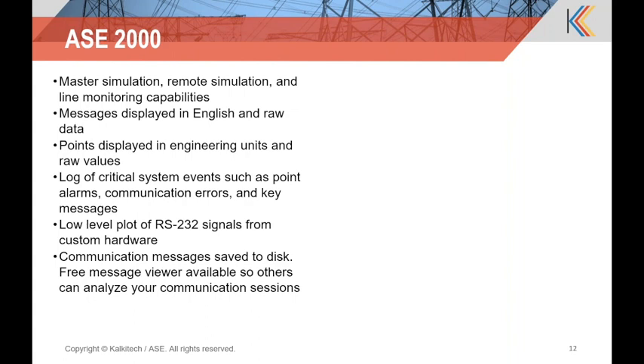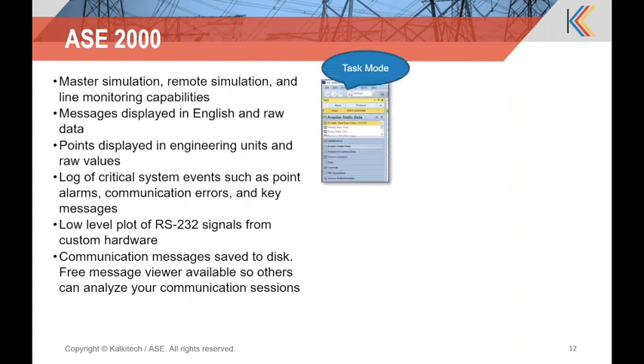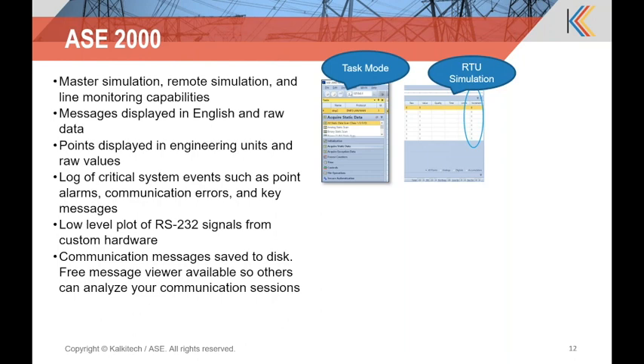So we have a few different modes of operation. We have a task mode in the test set, which is a predefined list of standard SCADA communications, such as data scans, exception scans for both binary and analog information. It doesn't take an expert or anyone with SCADA expertise to be able to define the parameters and initiate basic communication testing using task mode. And then with RTU simulation, we can toggle points, increment analogs, and totally simulate a realistic RTU or IO type environment.